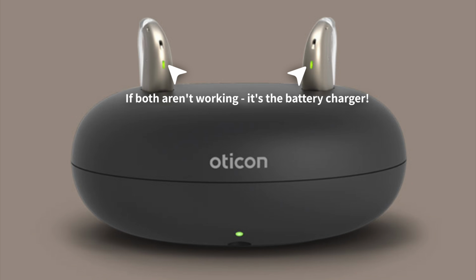If you put both of your hearing aids into the charger and neither one of them light up, it is extremely rare to have both lithium batteries go out at the same time. So it's probably not the batteries, it's probably the charger that's having the issue. I would first carefully clean your charging ports using a cotton swab soaked in alcohol, and you want to be really careful while you're doing this, but sometimes there can be some debris that works its way down inside of the charger that you need to get out. If that doesn't fix the issue, you want to unplug your charger and plug it into a different outlet, or change the charging cable if it's a removable charging cable.